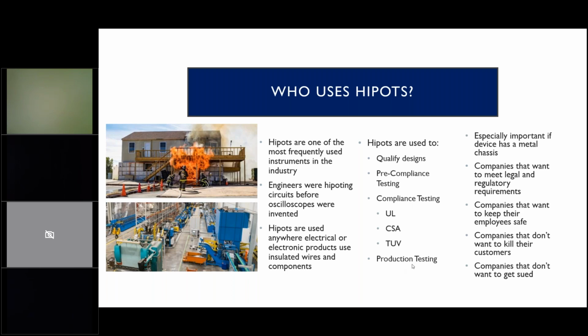Production testing, usually the test is a little faster. Qualification tests are a lot of times 60 seconds. Production tests are a lot of times 1 second. But it's important to test every product to make sure it's been built correctly and that you have good insulation that's wired properly. That's especially important if the device has a metal chassis. So I have seen people HIPOT plastic vacuum cleaners because if you have a screw that's exposed and maybe that screw goes into the chassis, it's possible even though the whole chassis is plastic, you could touch the screw and get shocked. Okay? But if it's got a metal chassis, that's the big danger.